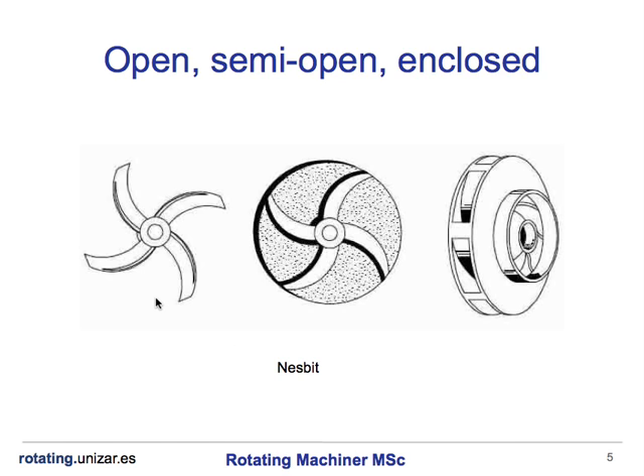If we look at whether the impellers have lids or not, we can classify the impellers as open, semi-open, or enclosed. The open impeller consists only of blades attached to a hub. It resembles a propeller. This impeller has low efficiency but it must be used when it is necessary to clean the impeller and when there is risk of blocking.